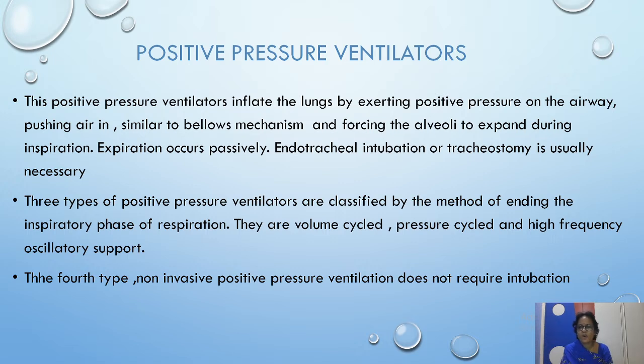And three types of positive pressure ventilators are classified by the method of ending the inspiratory phase of respiration. They are volume cycle, pressure cycle, and high frequency oscillatory support. The fourth type of positive pressure ventilators is also available, which is called non-invasive positive pressure ventilators, which does not require any endotracheal intubation or any tracheostomy.